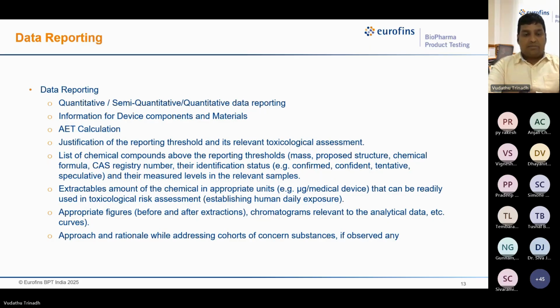Then the extractable amount of the chemical should be reported in appropriate units. If you are measuring any specific leachable in terms of μg per ml, then that should be converted into μg per medical device, considering the medical device clinical use conditions. Then appropriate figures, like before and after extractions, chromatograms, and any relevant analytical data, should be reported. Next, any rationale for the concerned substances, if anything was observed, should also be captured as part of reporting.